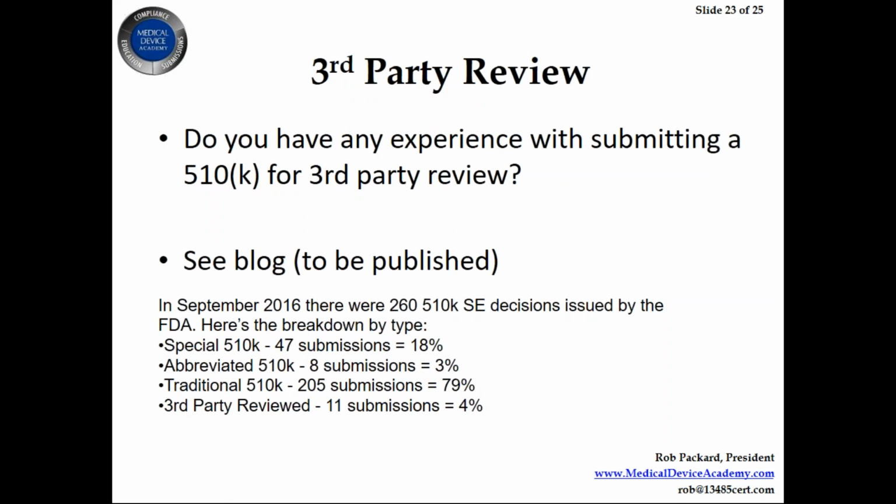The next question was about third-party reviews. Do I have any experience submitting a 510K for third-party review? I personally have never submitted something to a third-party reviewer. And part of that has to do with the products that I have worked on weren't eligible for third-party review. Very few products are actually eligible for third-party review, and the third-party reviewers only have certain product classification codes that they can actually do that for.